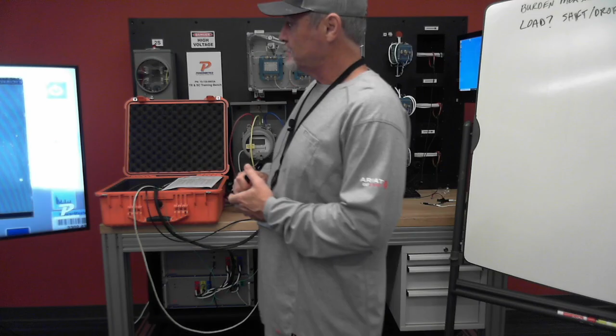Thanks, JP. Way down, right? It wasn't seeing much at all. And we've mentioned this before. If I get one error after another out there testing - a cross-phase connection, low primary current input, and polarity reversal - if I see all three go bing, bing, bing in a row, typically that means I should have probably looked at my load first, but then again it could have been a load change. That's usually indicative of a very low load, okay? So the machine's saying, this just isn't going to work, it's too low for me. And that's when you look and see 0.1 secondary amps or something like that.